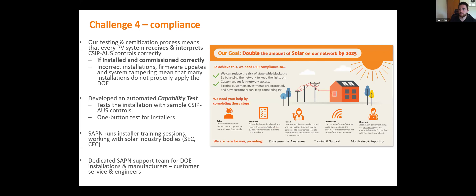To tackle this, we developed the capability test — an automated test of the installation before it starts receiving a true DOE, by applying sample CSIP-AUS controls. This tests that the inverter is properly connected to our server once installed, connected to the customer's internet, and registered with us. It's a single-button test for an installer, simplifying the commissioning process. We also run ongoing training sessions with solar installers, retailers, and manufacturers via peak bodies such as the Smart Energy Council and the Clean Energy Council. We have a dedicated team for installer support on DOE systems, plus operational engineers who support installers, solar retailers, and inverter manufacturers through commissioning, testing, and certification.